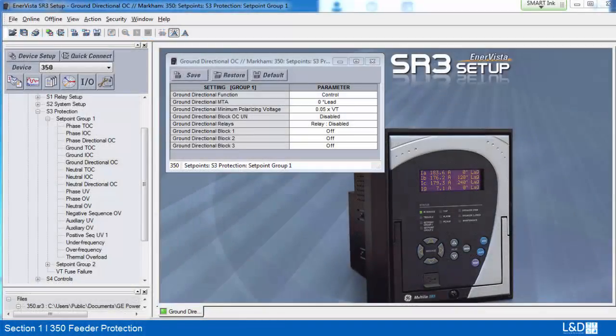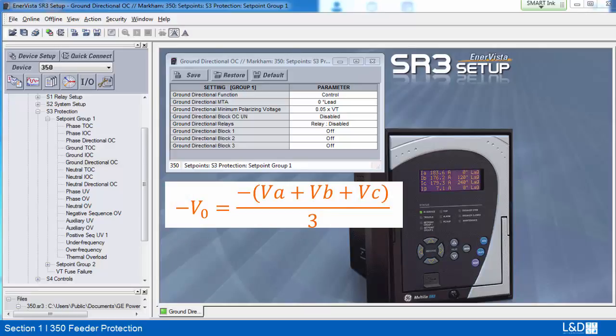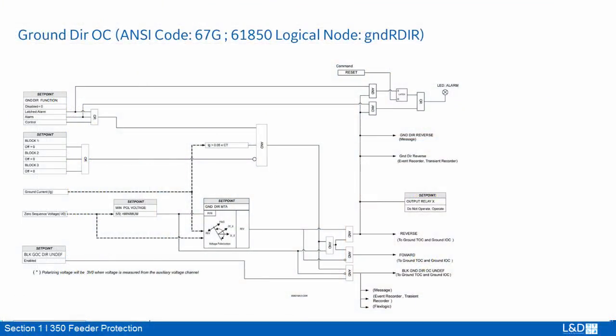The ground directional element is used to discriminate fault directions of ground IOC and TOC. Polarizing voltage can be either calculated when three-phase voltages are available and in Y connection, or 3V0 measured from the open delta VT to input Vx. The operating current for the ground directional element is the measured current from the ground CT input terminals, which can be either the current from a zero-sequence CT or the zero-sequence current from a residual CT connection. From the logic diagram, the polarizing voltage is V0 when calculated or 3V0 when using auxiliary VT inputs.